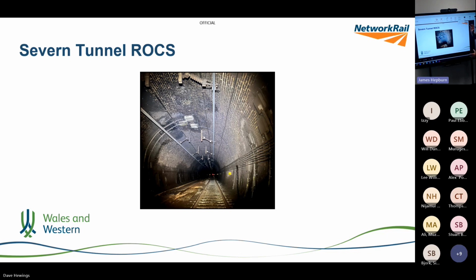But that was one issue. The corrosion started to become a significant point, even by 2017, 2018. In fact, there were sections where the aluminium beam had corroded when in contact with the copper to the point that the copper wire fell out of the beam. So even at that point, something had to be done. Now, that raises the issue of what do you do? The aluminium will always be susceptible to electrolytic corrosion in contact with copper. Even copper and steel will have electrolytic corrosion if in an electrolyte environment, which there is.